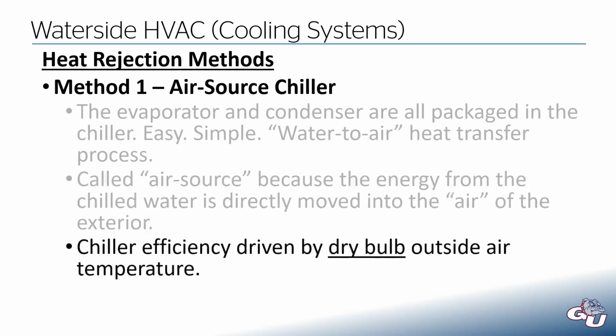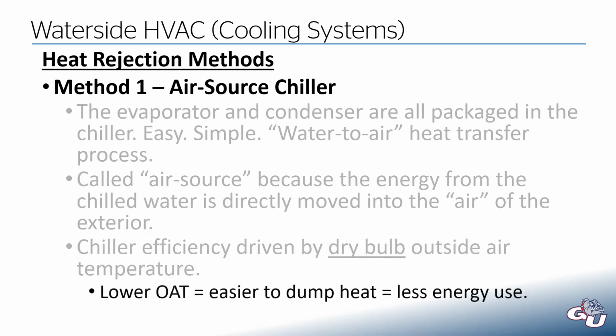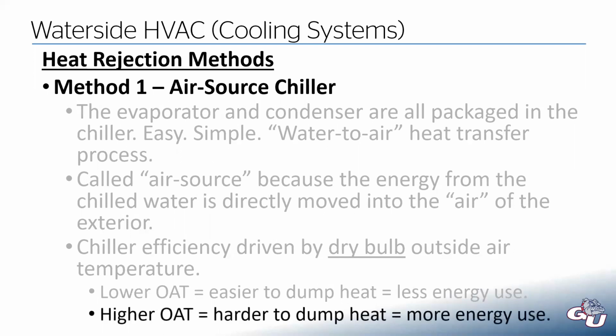The efficiency of our chiller is going to be driven by our dry bulb outside air temperature. If it's a little bit colder outside, it's easier to reject that heat, and that's going to lead to less energy use at the chiller. But if we have a higher outside air temperature, then it's harder to reject that heat to air that's already hot, and our chiller is going to have to work harder. So the dry bulb outside air temperature is the primary driver of our efficiency.